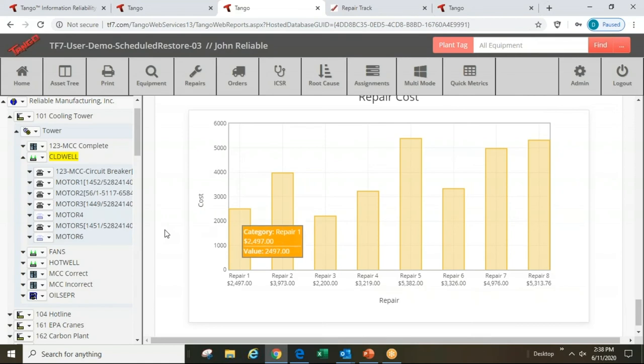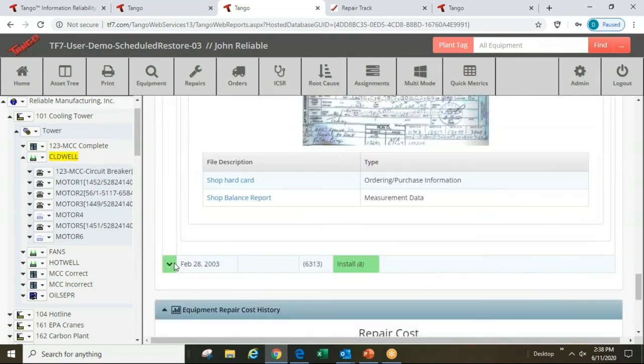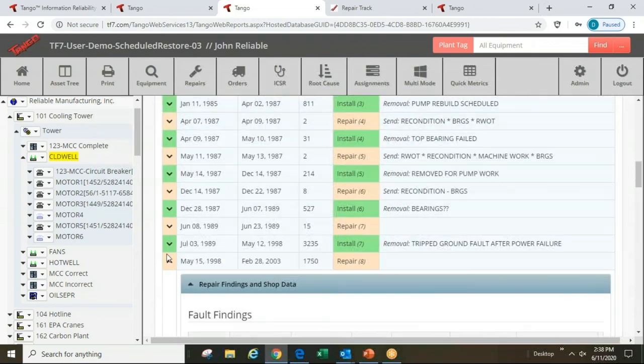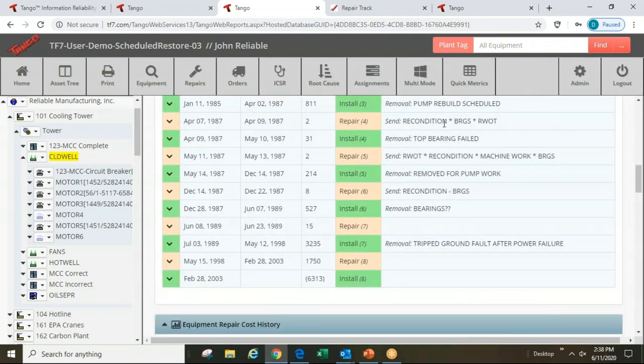Long story short, this is something that happened way too often. For 15 years, the majority of failures were related to water intrusion into lubricant at this cold well pump location — spending several thousand dollars per repair in repetitive failures — before it was finally determined to either shelter the location from water or add shaft seals to the motor itself as part of the repair.